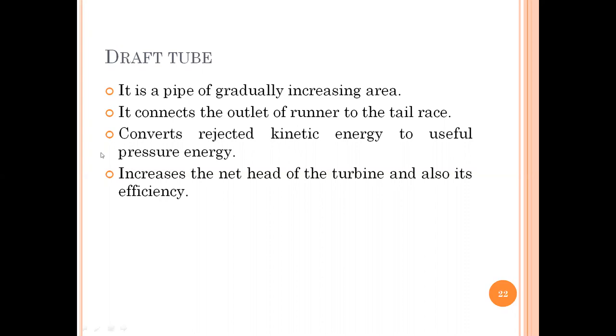A draft tube is basically a pipe of gradually increasing area. Section one is attached to your runner casing, and section two is at your tail race — the area is increasing. It connects the outlet of the runner to the tail race, immersed inside the tail race. The tail race is the level of water downstream of a dam, and the draft tube converts rejected kinetic energy to useful pressure energy.